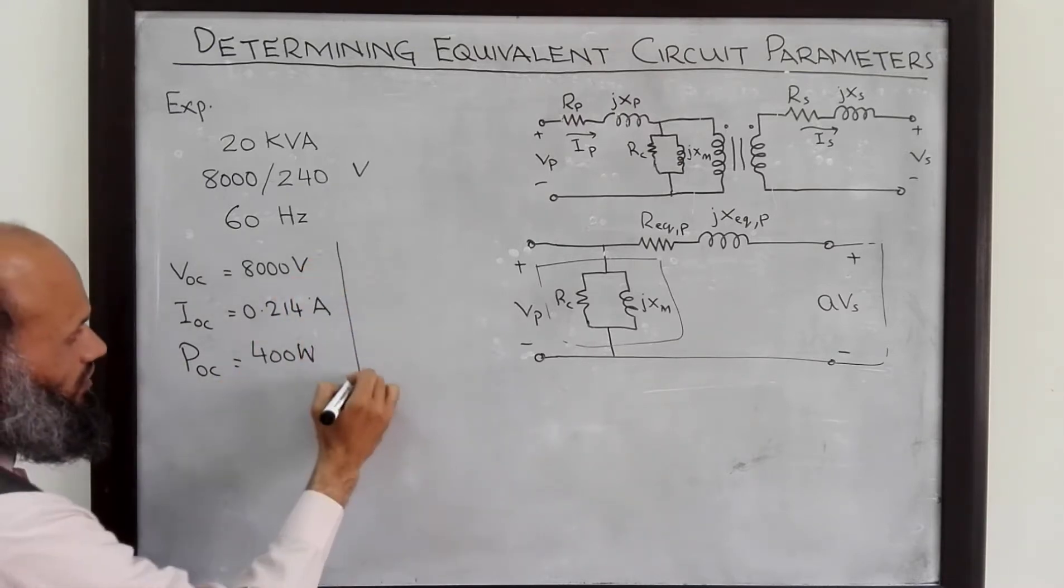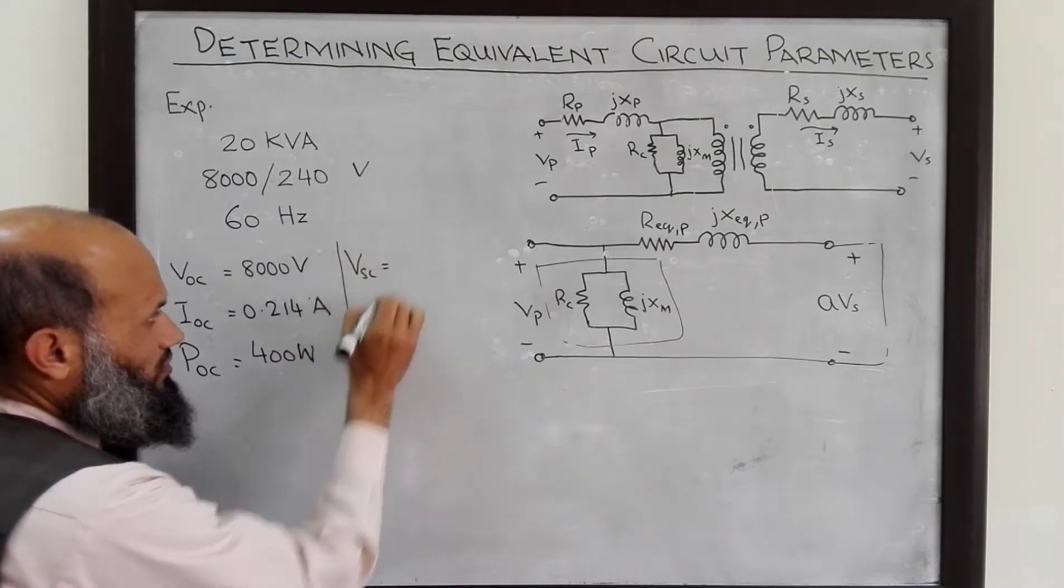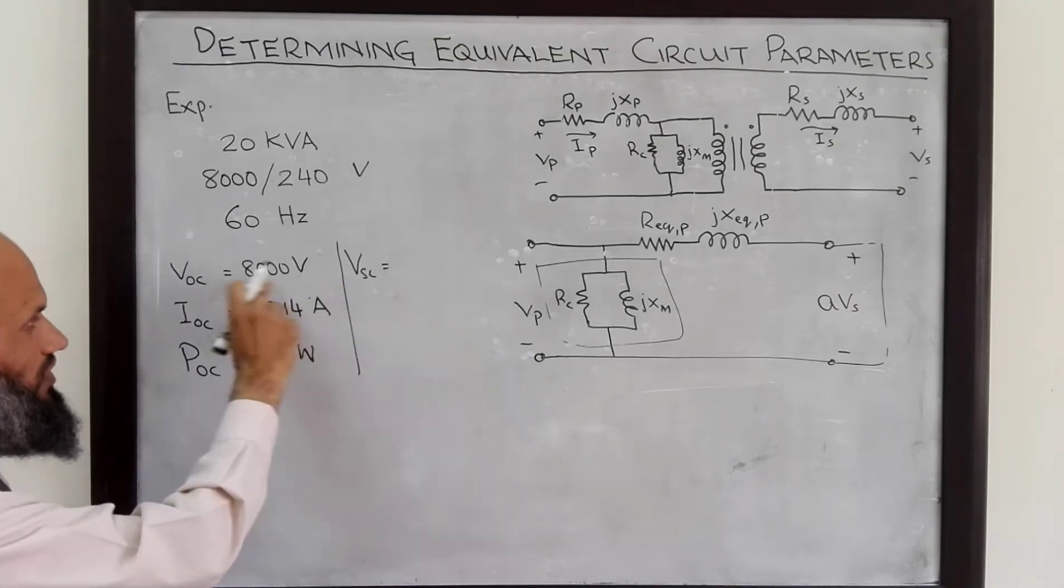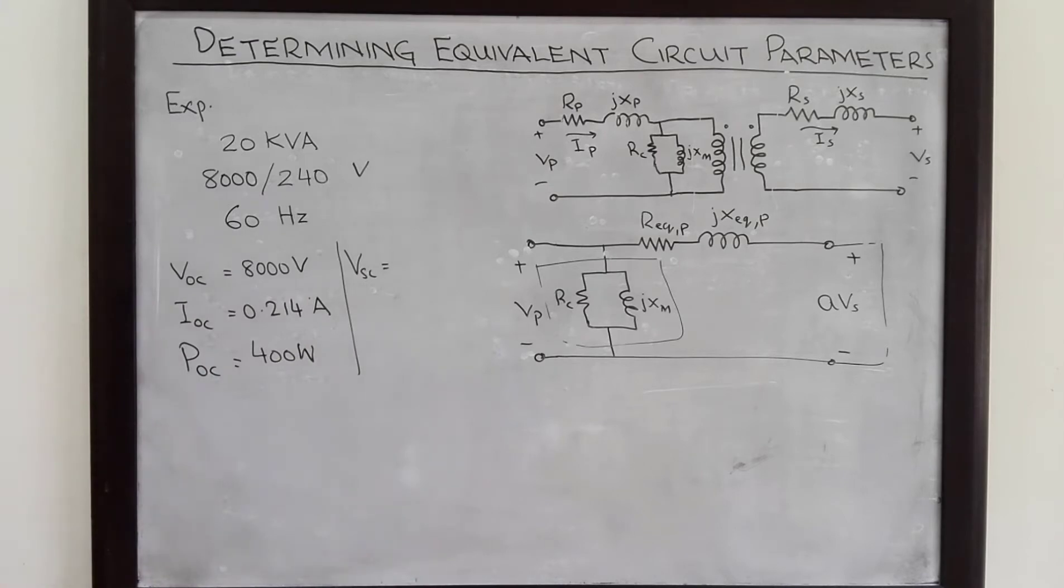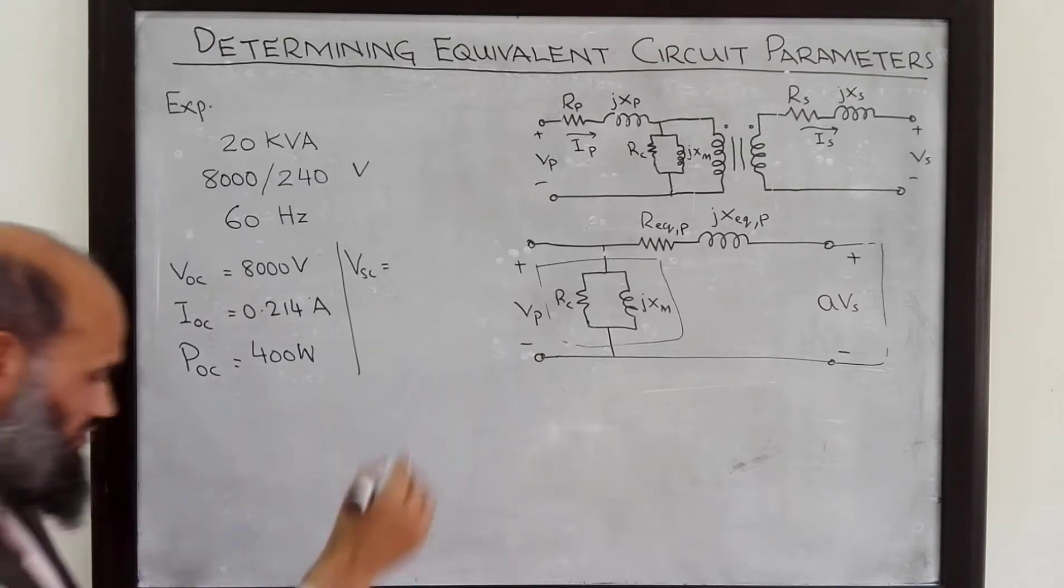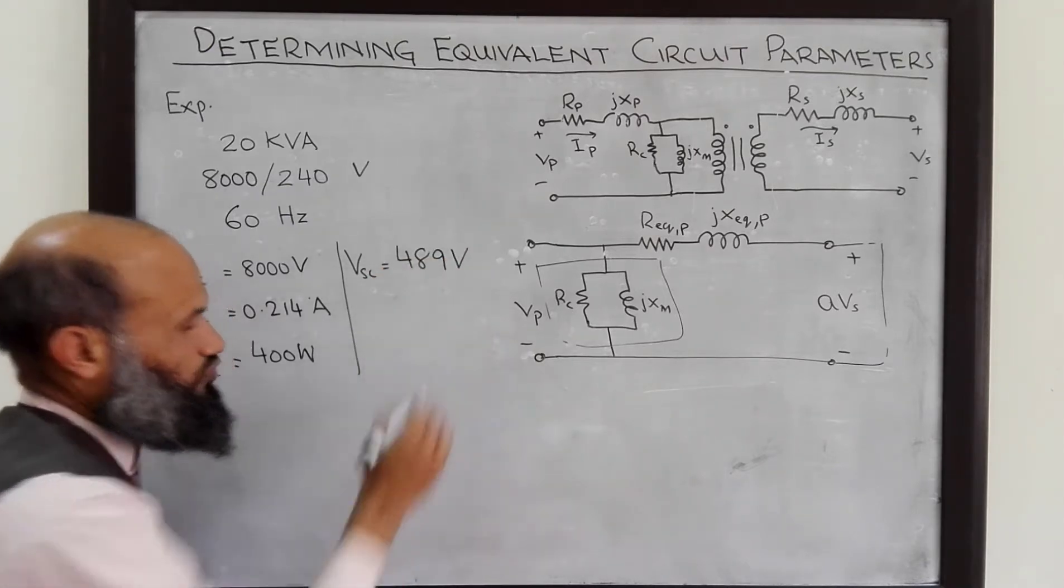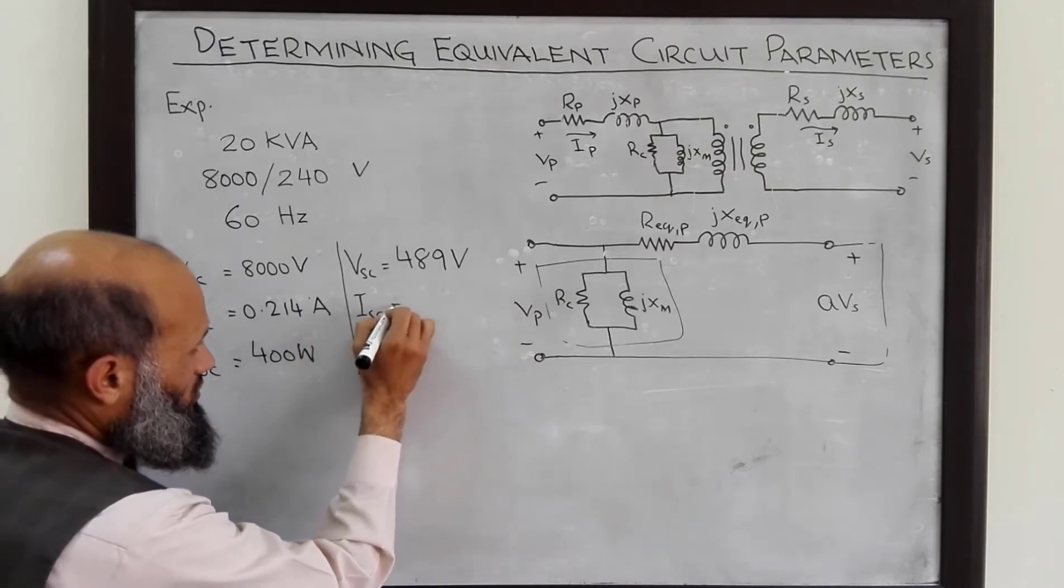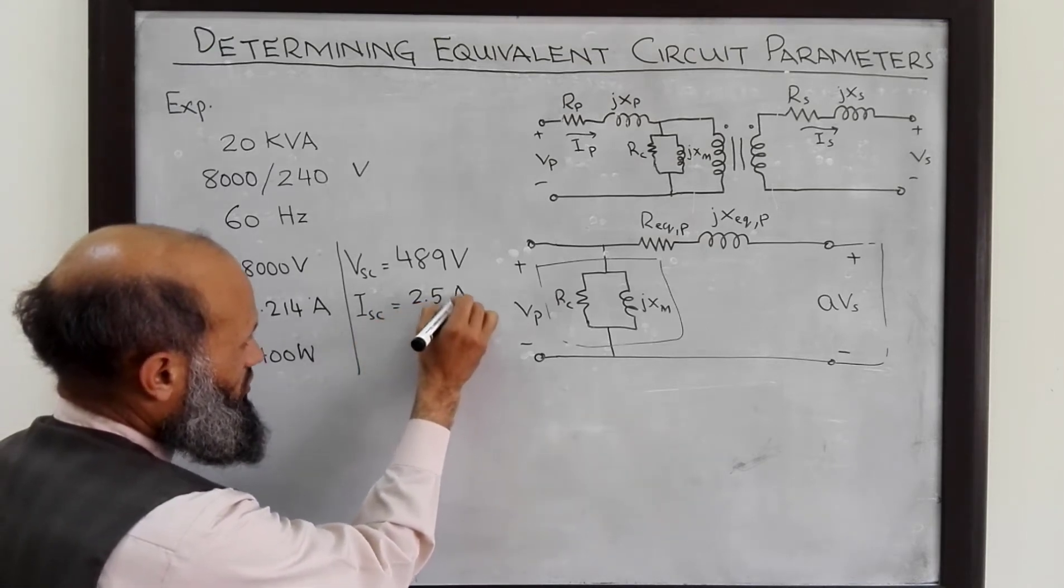Similarly, we perform the short circuit test and the short circuit voltage. To perform the short circuit test, we do not apply the rated voltage. Rather, we apply a small voltage such that the rated current flows in the transformer. So, the voltage which is applied to this transformer is 489 volts. And the current that flows in the short circuit test is the rated current, 2.5 ampere.